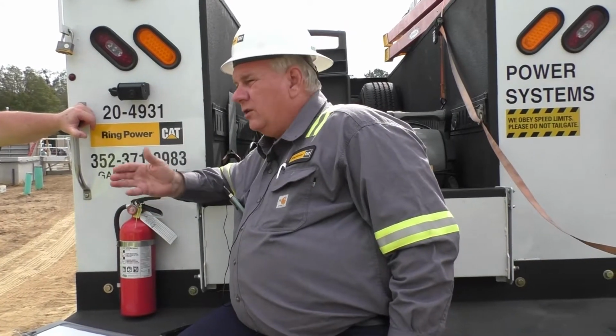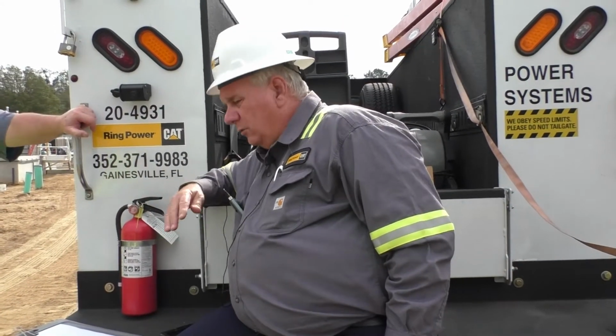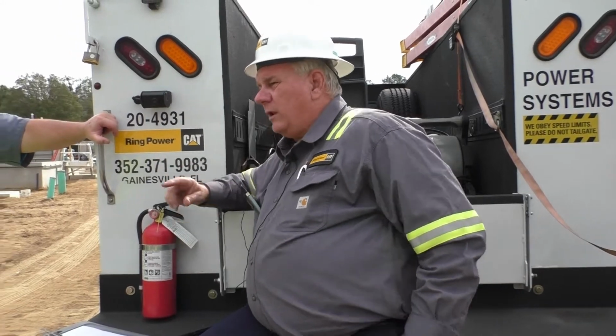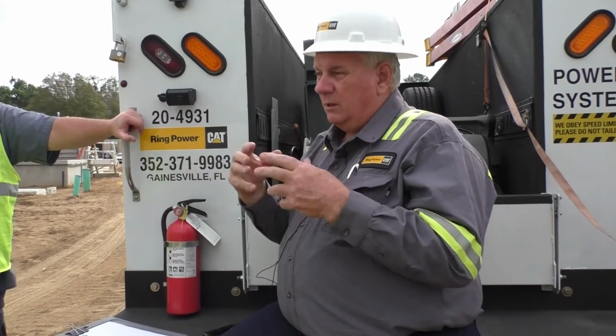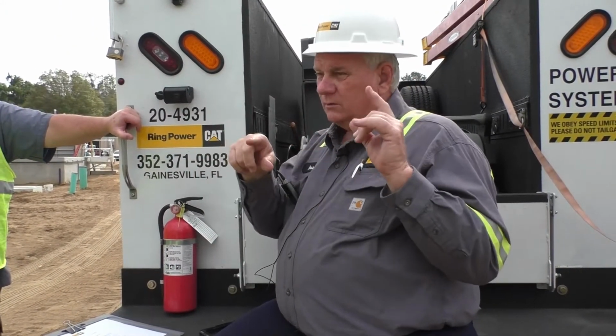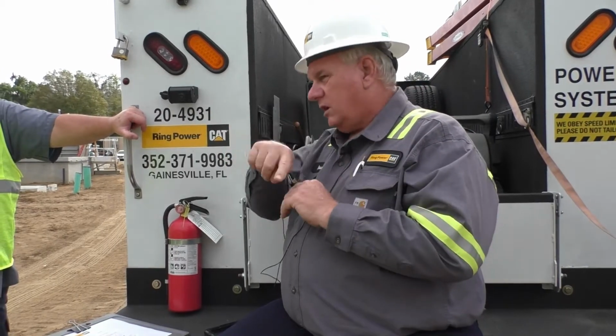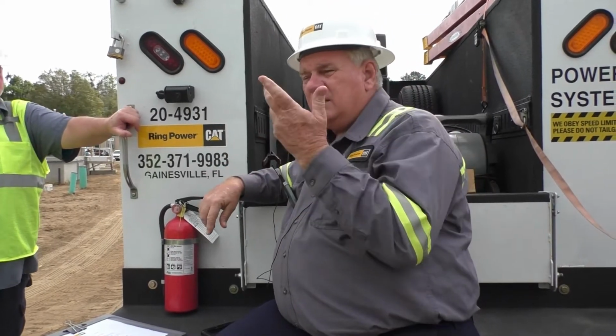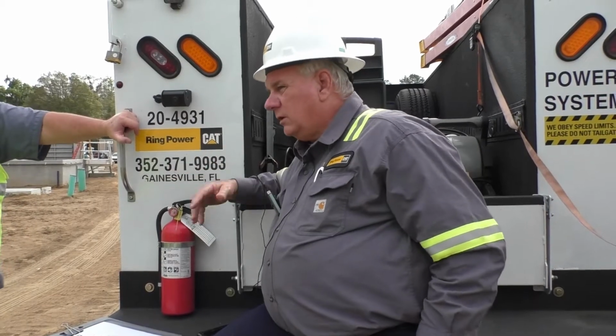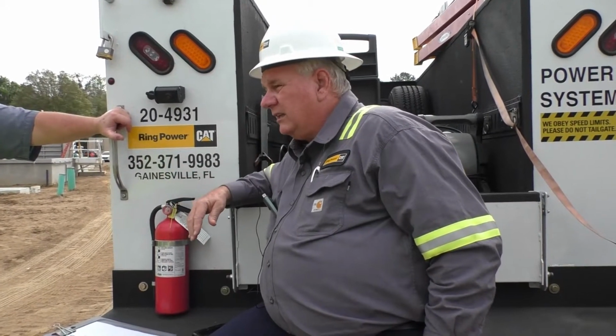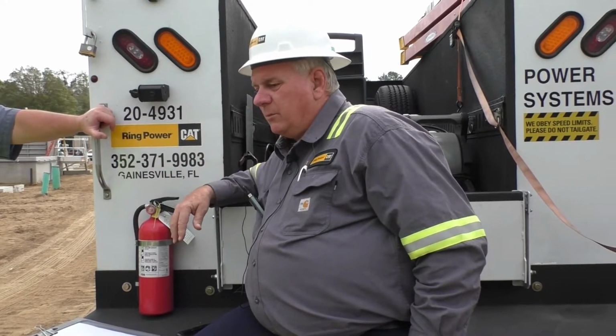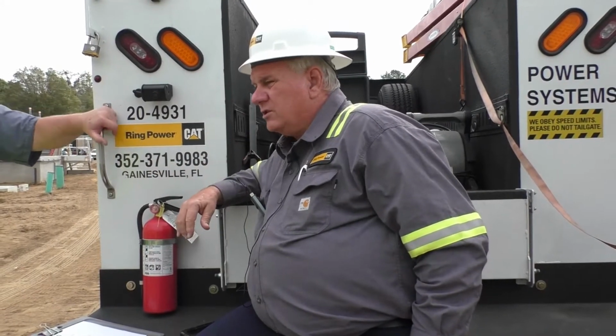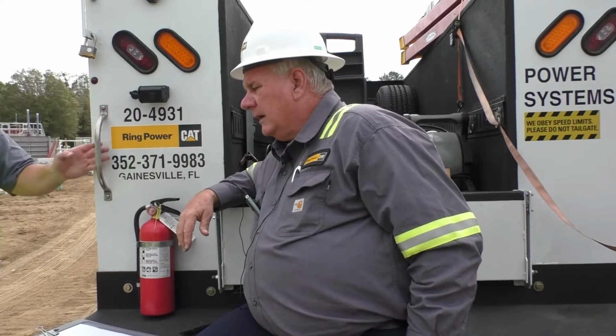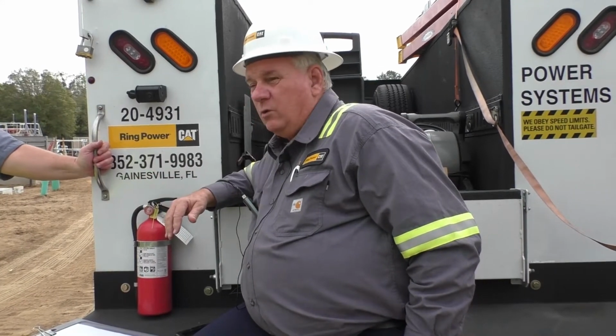And what you're trying to do there is let all your motor loads decay, and to restart them from scratch, so you don't have, as motors wind down, they become generators, and you don't want that voltage and frequency running into this voltage and frequency, and you get a big high inrush peak and possibly a breaker trip for a device or a motor. So I'm sure that's why they did it. I've set the breaker to the coordination study per the engineer. Are there any questions before we start?